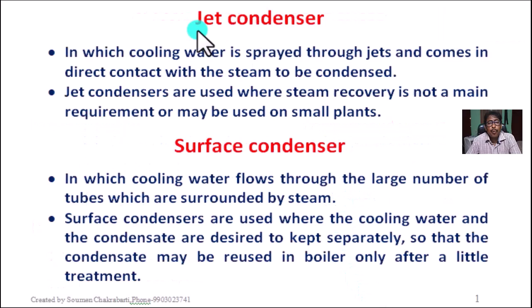Okay, what is jet condenser? In which cooling water is sprayed through a jet. Cooling water is sprayed through a jet of water and comes in direct contact with the steam to be condensed. Steam and water are directly mixed up. Jet condensers are used where steam recovery is not a main requirement, or may be used on a small plant.